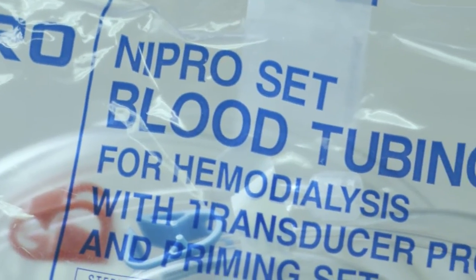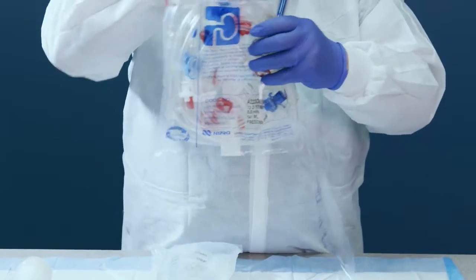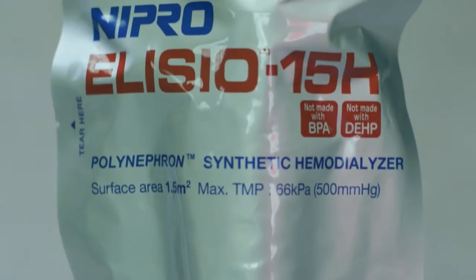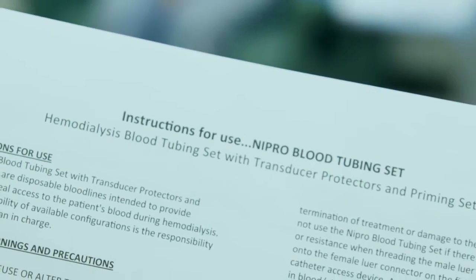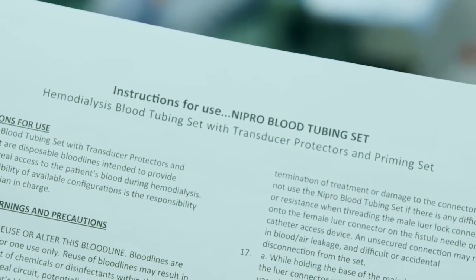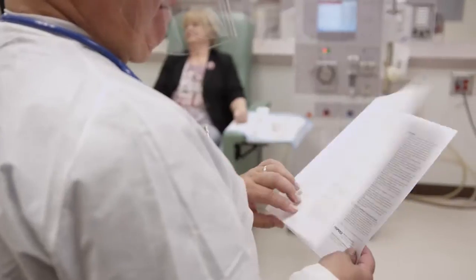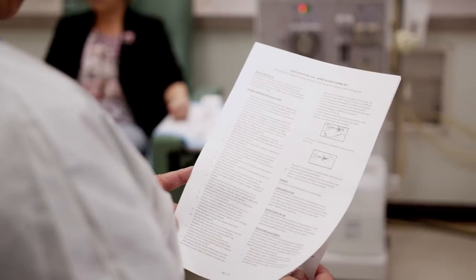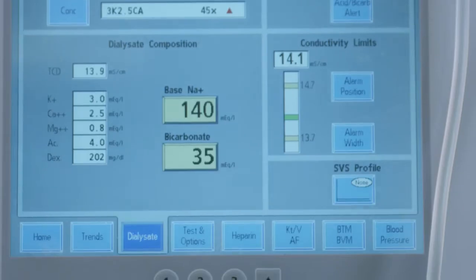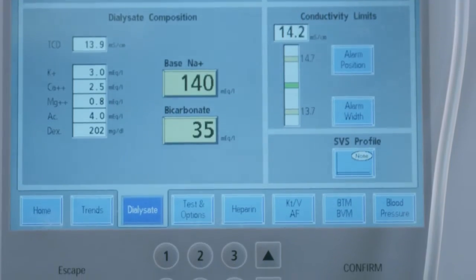Nipro also manufactures blood tubing sets compatible with other hemodialysis machines in the market. Before use, be sure to read the instructions provided to fully understand the benefits of the NiproSet blood tubing and its proper use. It's important to calibrate your hemodialysis machine for the NiproSet. Patient safety depends on proper calibration of your equipment.